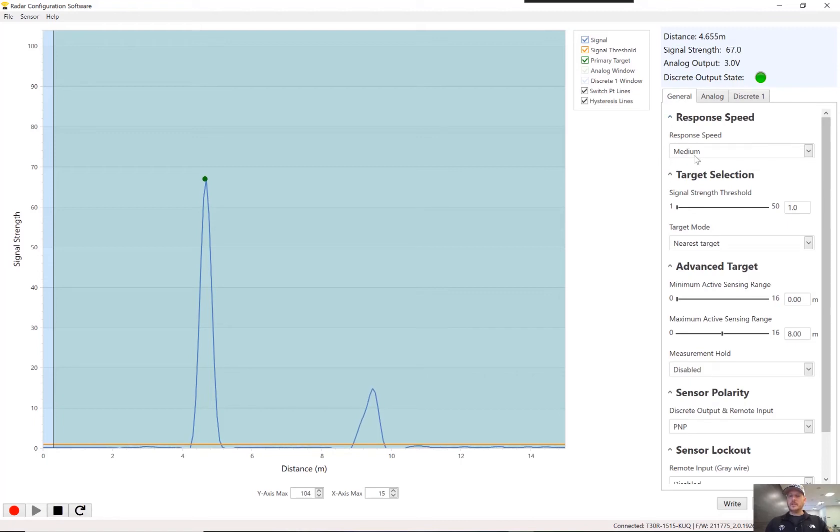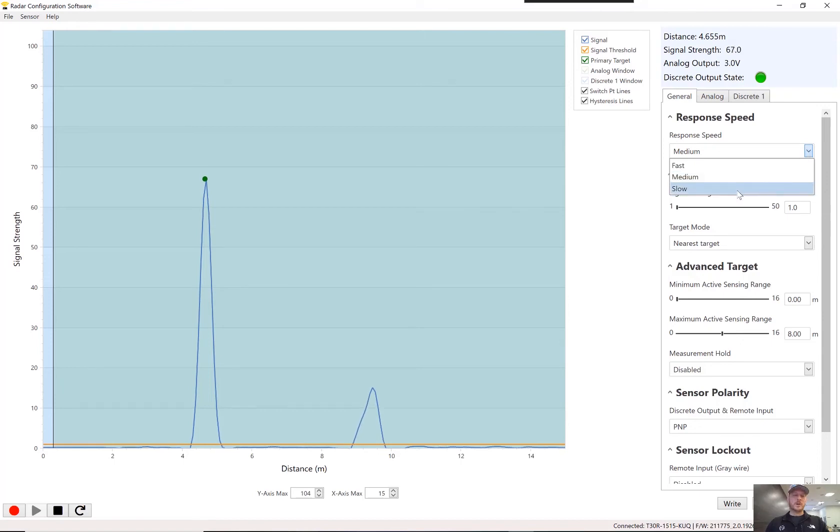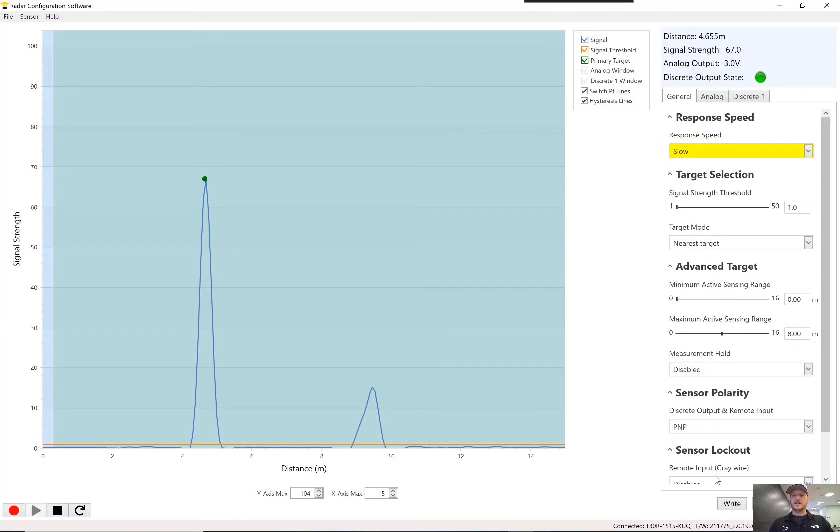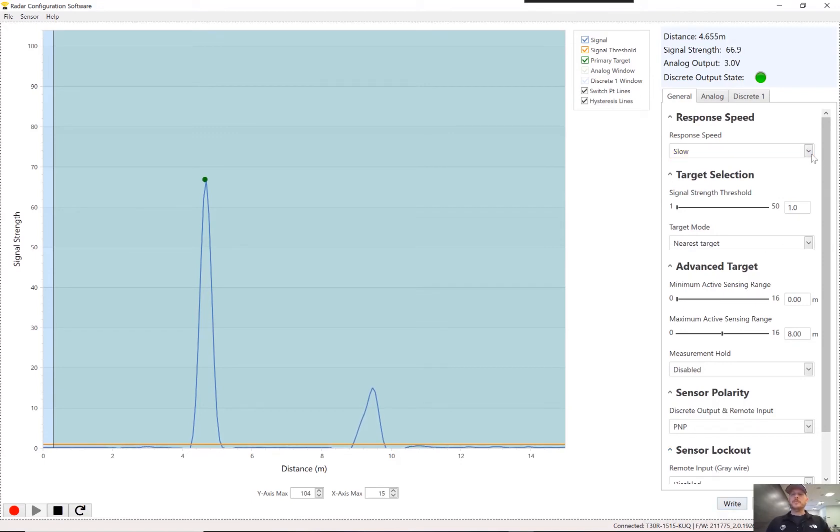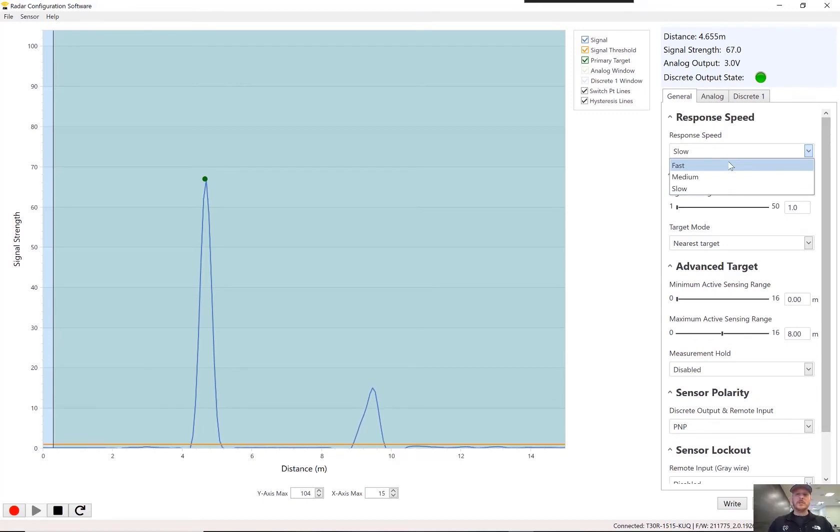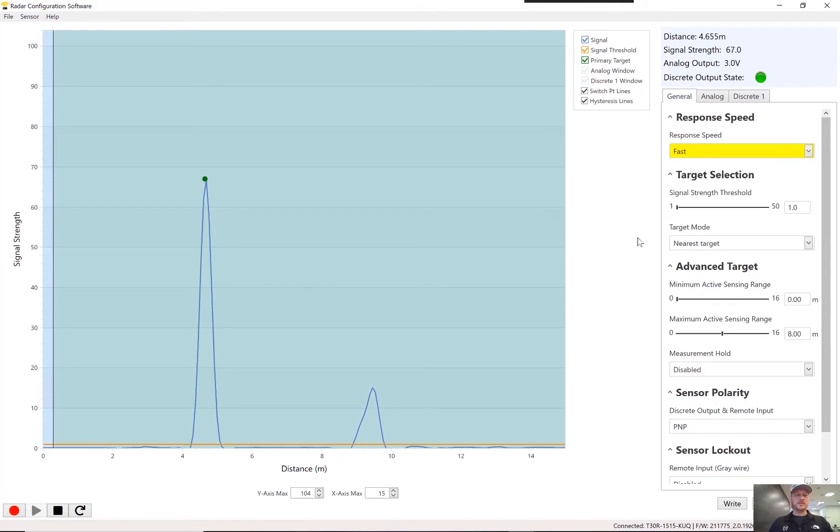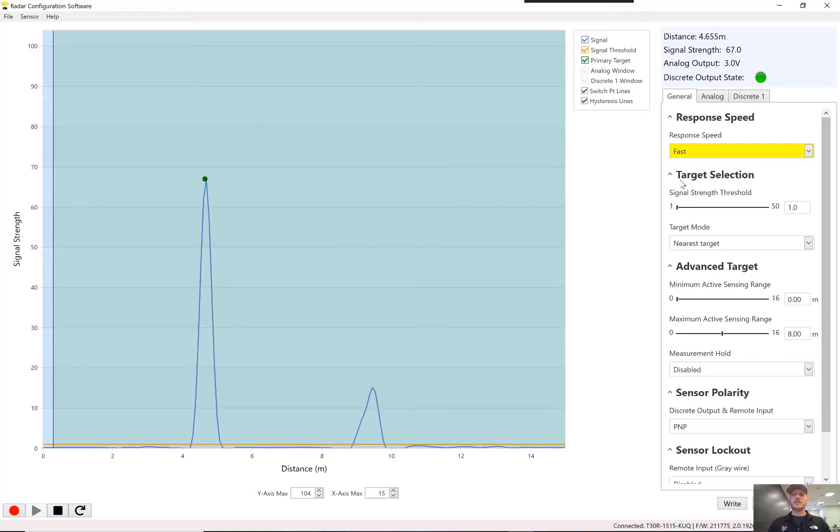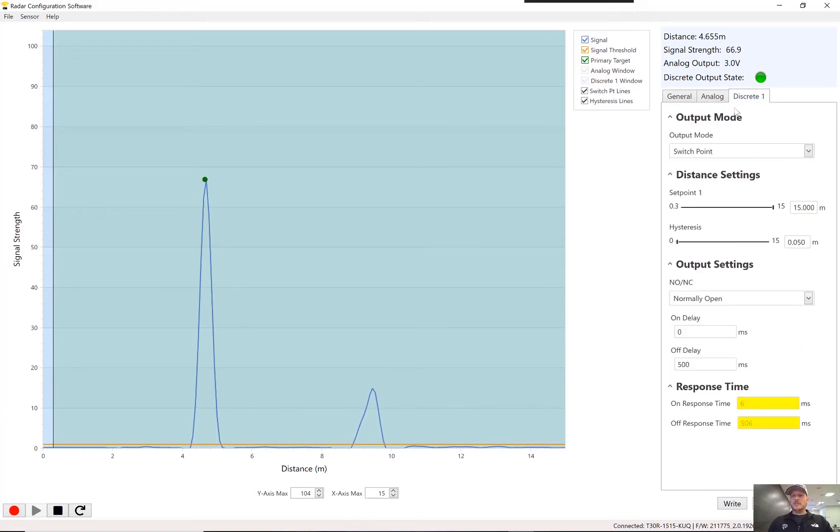A couple of things that I should have mentioned here is response speed. The slower the response speed, the better or the stronger the target signal will be, but it will also be a slower response time. For this application that I'm doing here as a demonstration, I want the fastest response time speed I can get because I want to be able to detect that cup essentially as soon as it's in the view field or in the area that I want the output to turn on. So we'll leave that at fast.